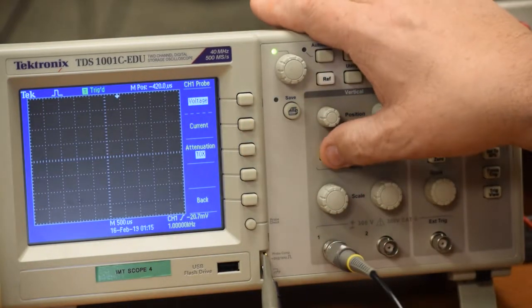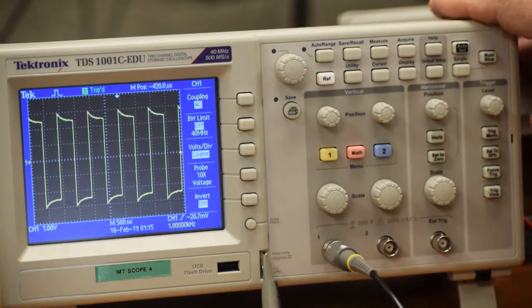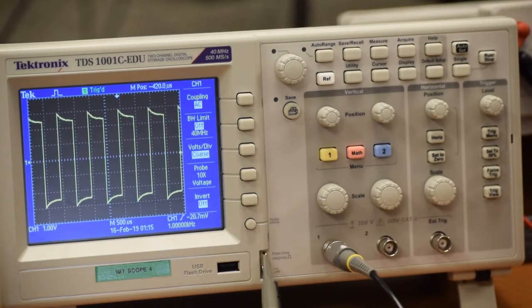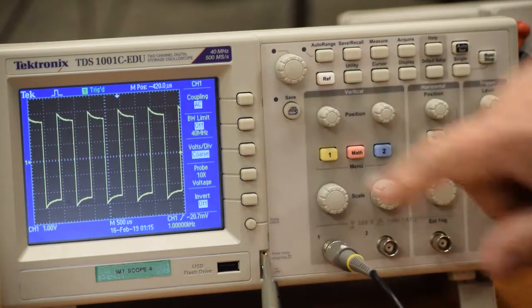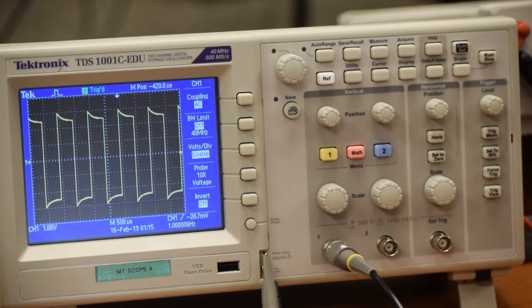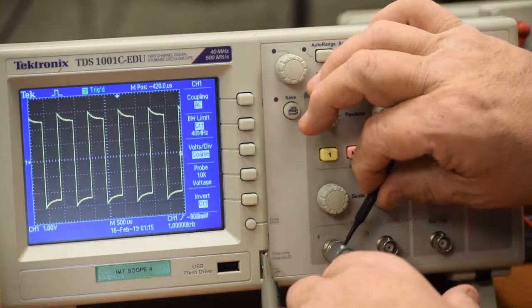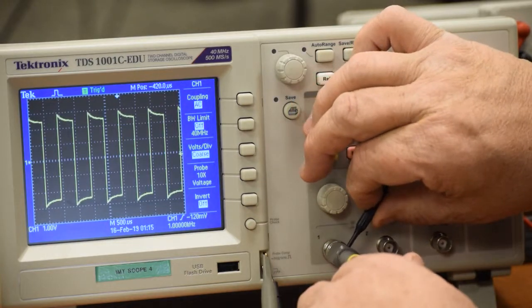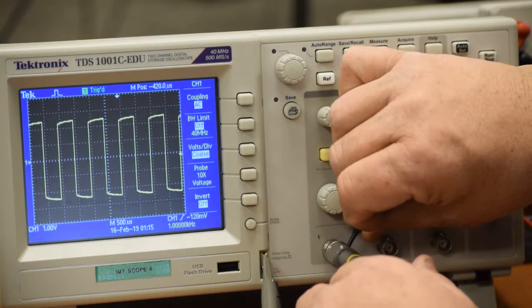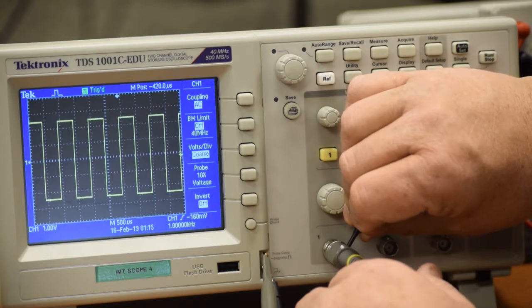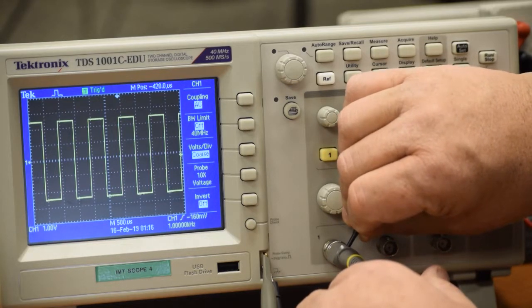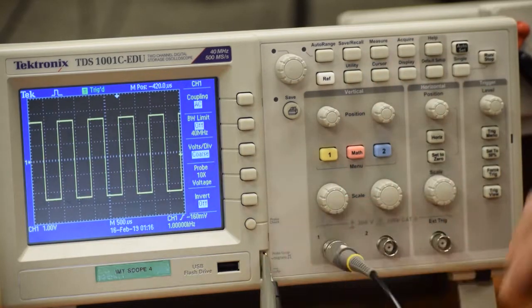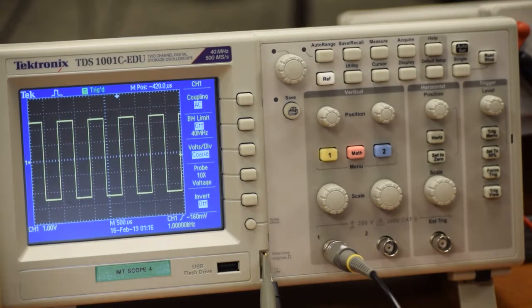But once they match up, you should be good. And notice the square wave is not a clean square wave on top, and that's what you're adjusting. You want that probe to be adjusted so that it's a nice clean signal. Your rises and your falls are exactly parallel. And then there you go. So that's how you would make the probe adjustment.